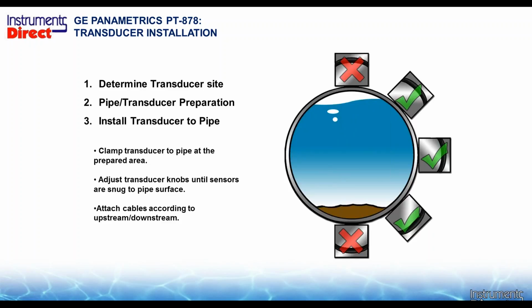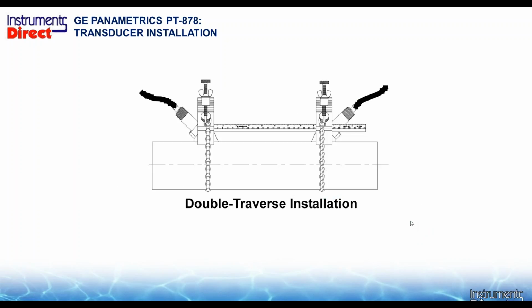If you're mounting your transducer, then the rule of thumb is, it doesn't make any difference really if it's vertical or horizontal, but the two places I prefer not to mount a sensor is at the top of the pipe and the bottom of the pipe. You can have some aeration at the top, and you can have some debris on the bottom. So anything on the side is fine if you have that opportunity. So again, these are best practices. When you can, try to get this, you may not always have that opportunity. So you had a subterranean pipe, and you get to the site, and the guy just dug out half the pipe. Guess what? You're on the top of the pipe.